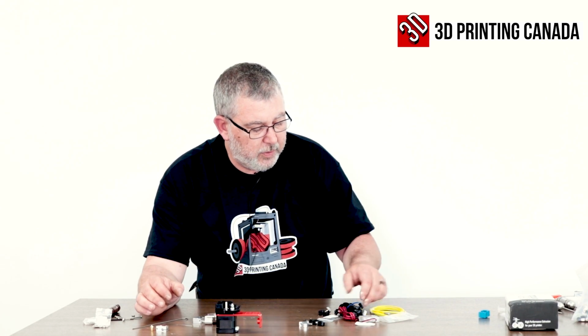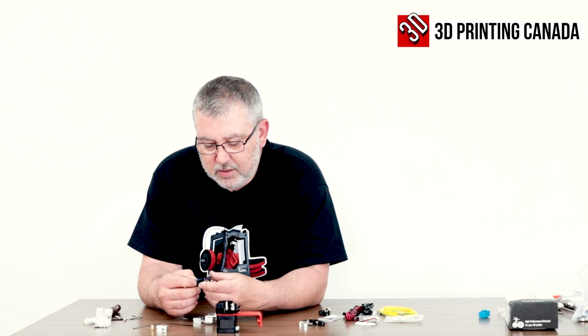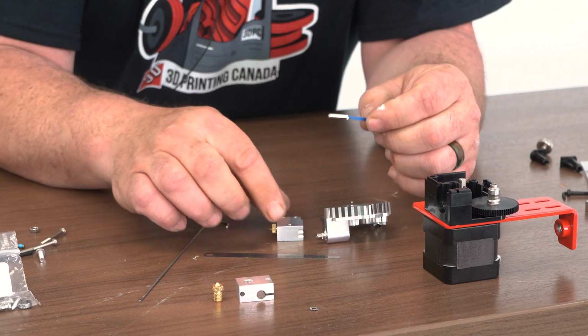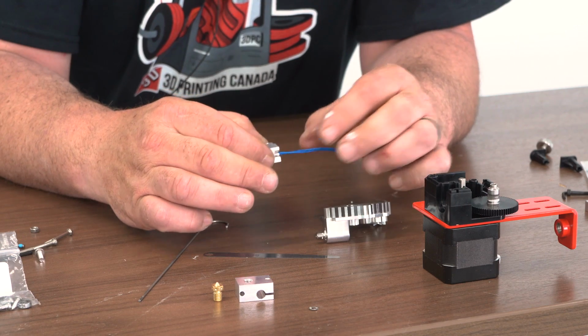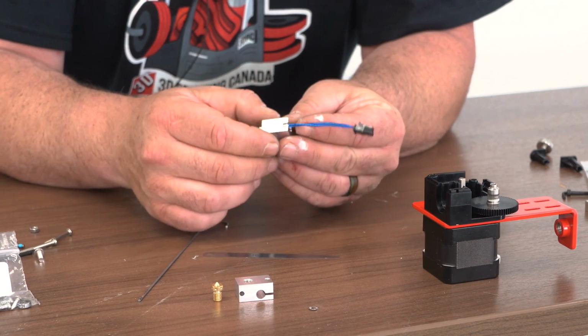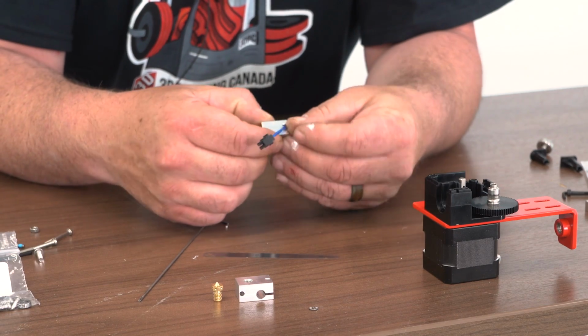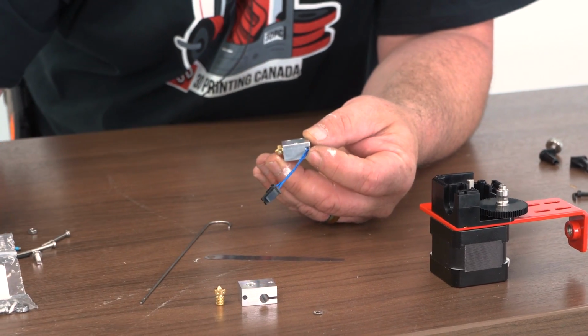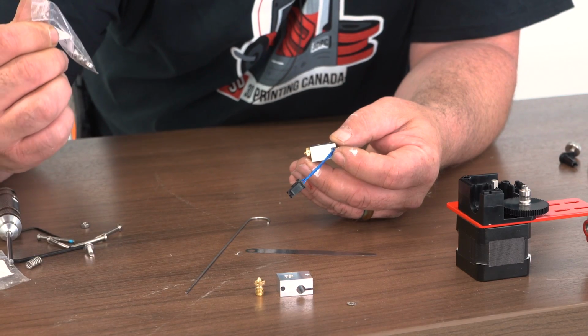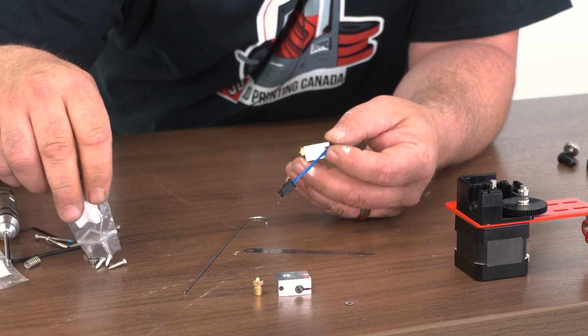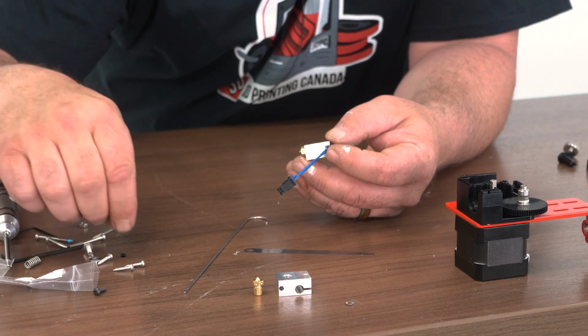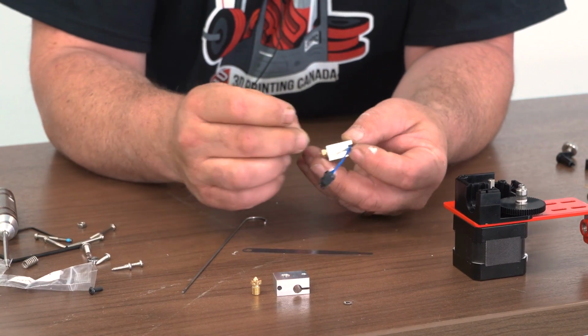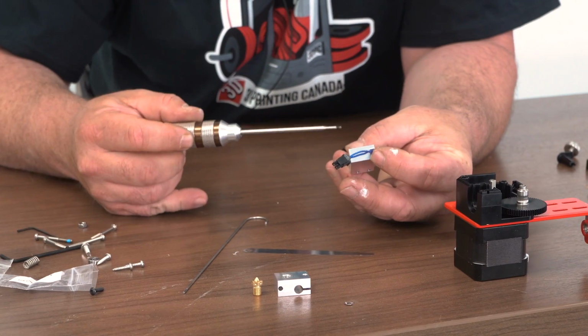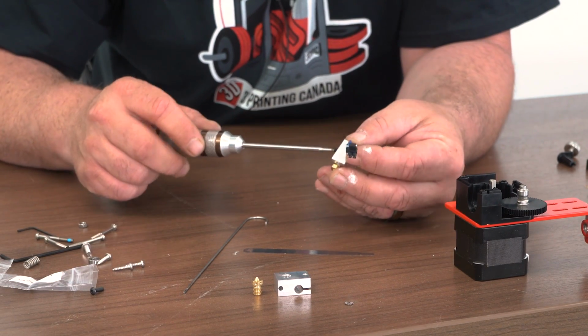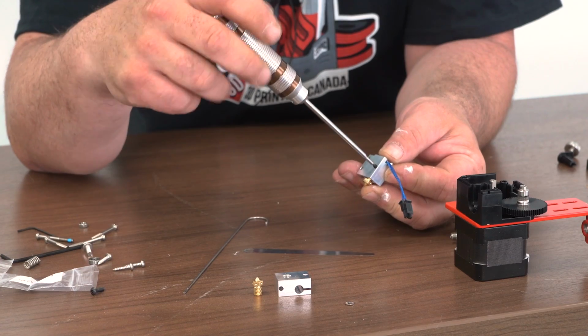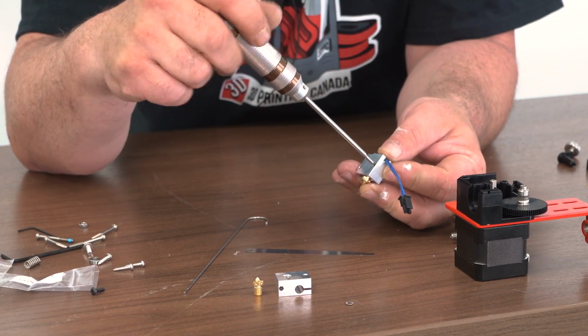Next, as you're assembling this together, you're going to want to install your heater cartridge. It goes in the front hole, and I usually pull it over into the notch in the front of the block. Then I pull out the black grub screw, also a 1.5 millimeter, and insert that in the small hole on the side of the block.